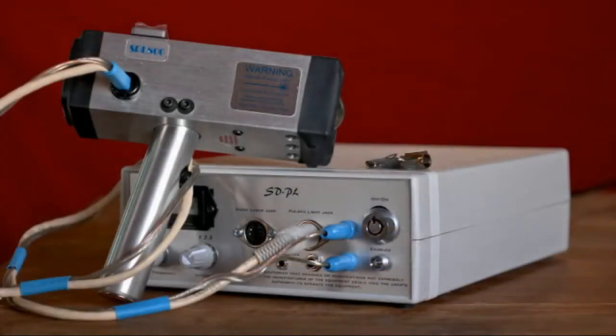The third handpiece that is driven by the control unit is an intense pulsed light gun. The two lasers are designed to produce a fixed light wavelength of 808 nanometers, very efficient in penetrating the skin, but the IPL uses a broad-spectrum bulb, which includes a mixture of wavelengths from 410 nanometers to 1200 nanometers.